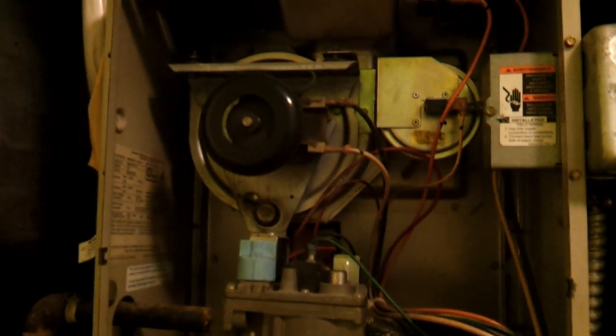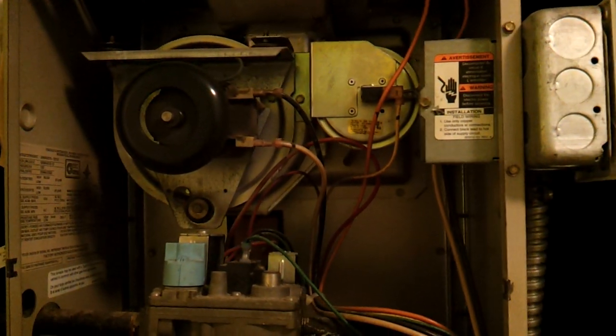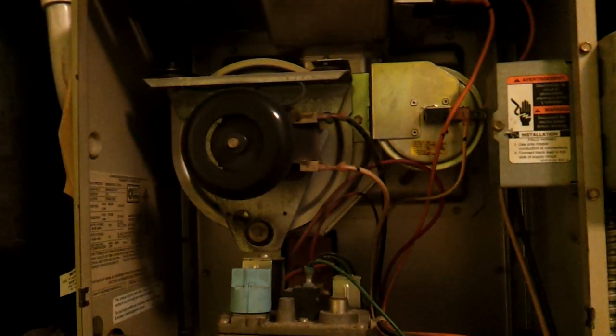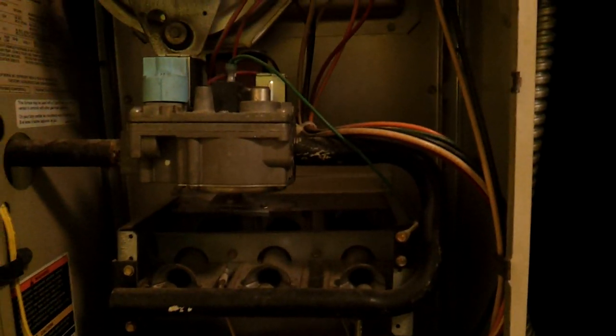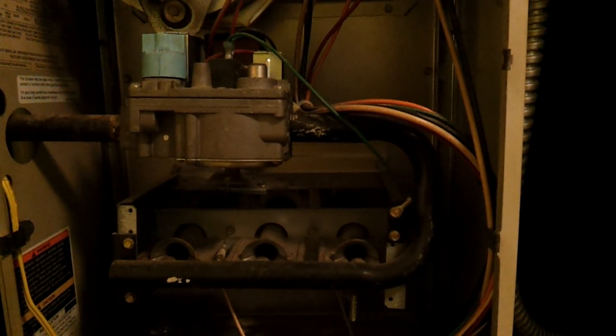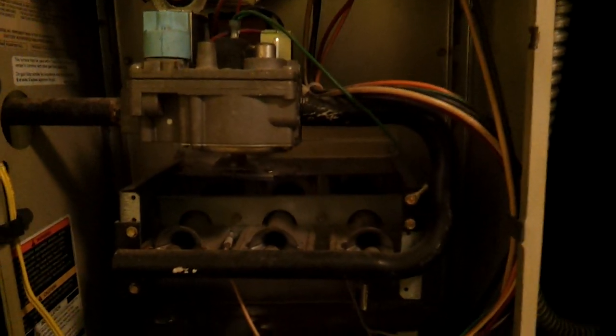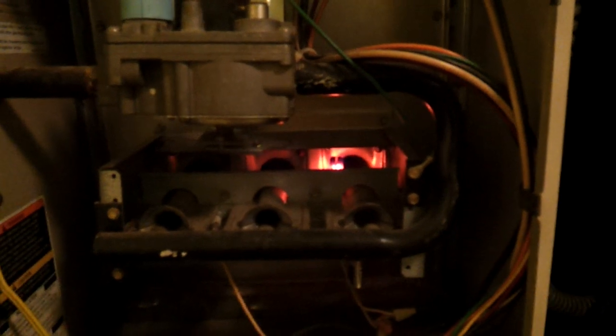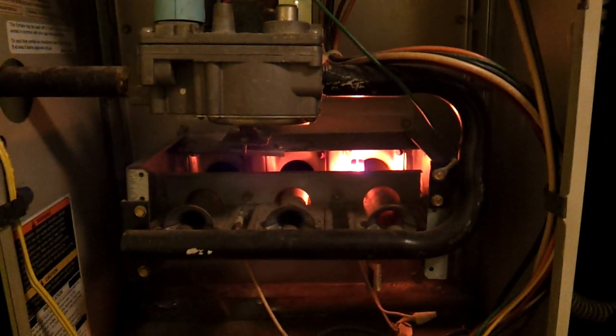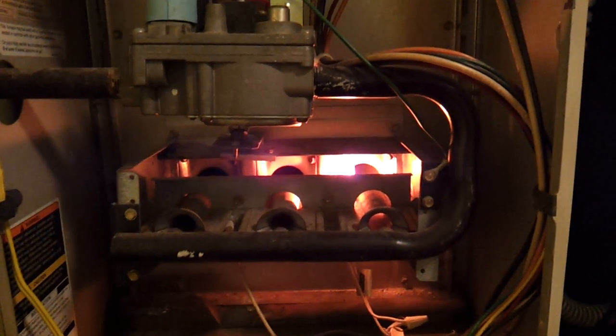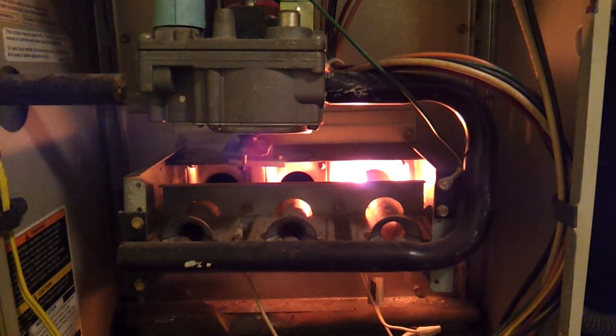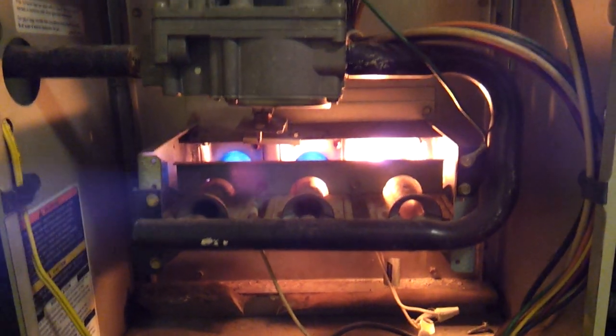There you can see the draft inducer is fired up, so it's going through what they call the pre-purge sequence, getting any remaining gases out of the heat exchanger. Now the blower is shut off while the heat exchanger warms up, so now the igniter is going to be coming on pretty soon. There it is. It's going to glow very brightly. It's very hot. That will cause the gas to ignite in a minute. There's the gas valve. And there's the 3 flames.